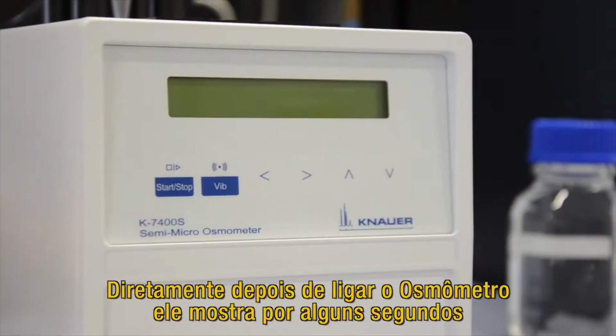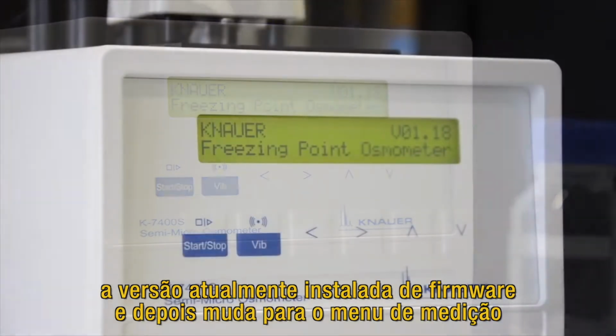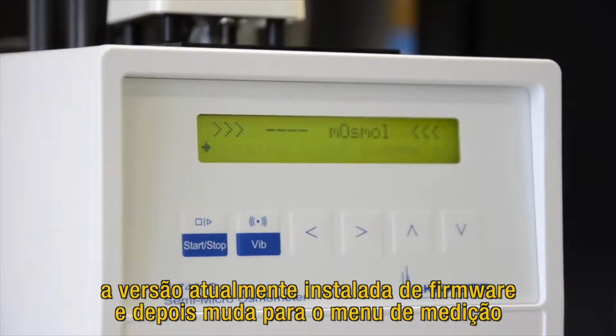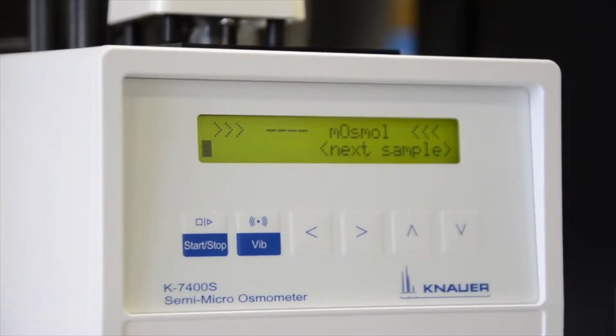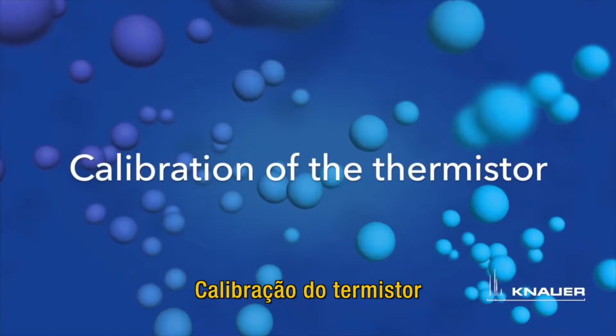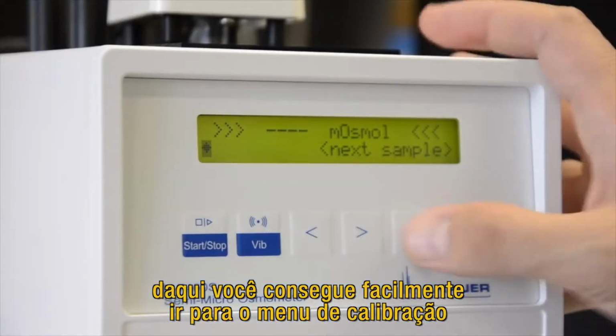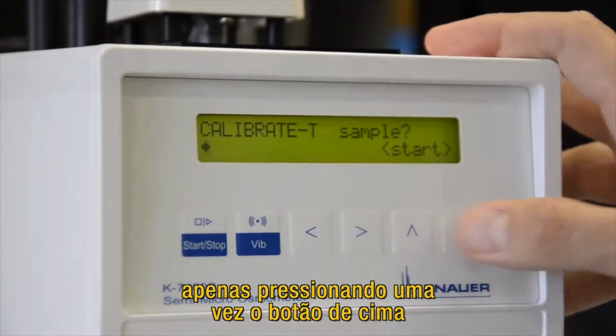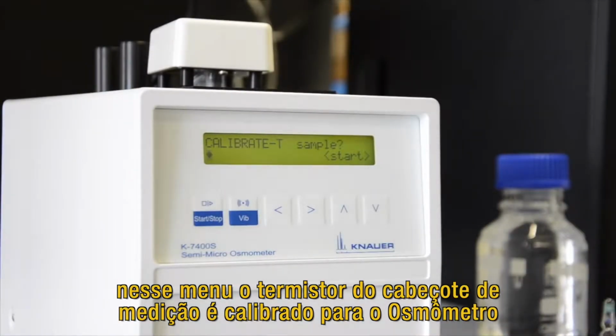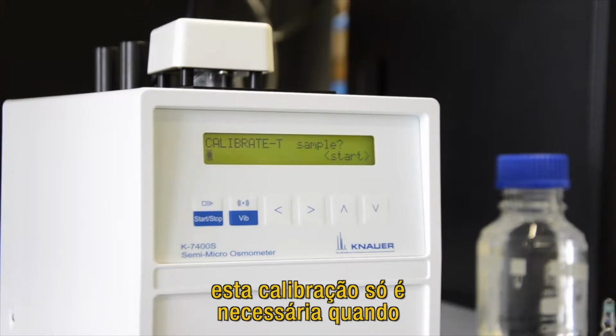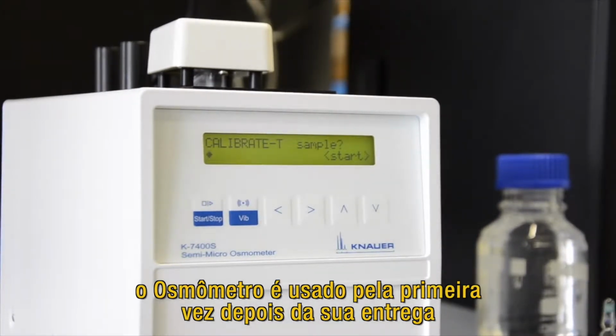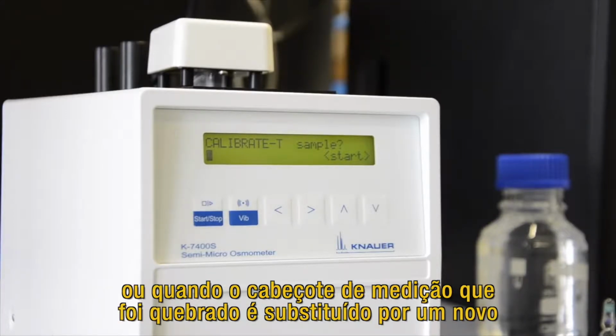Directly after turning on the osmometer, it shows you for some seconds the currently installed firmware version and then switches to the measurement menu. From here you can easily go to the Calibrate T menu by just pressing once the up button. In this menu, the thermistor of the measuring head is calibrated to the respective osmometer. This calibration is necessary only when the osmometer is used for the first time after delivery and when a broken measuring head was replaced by a new one.